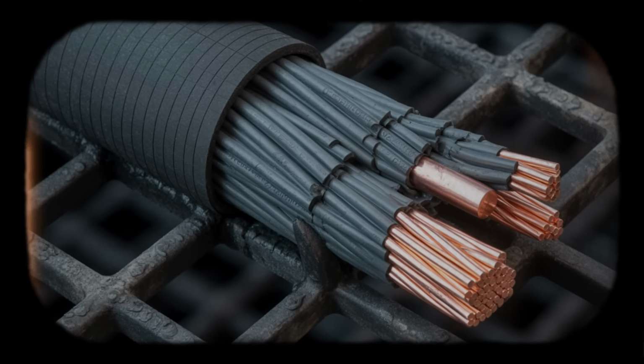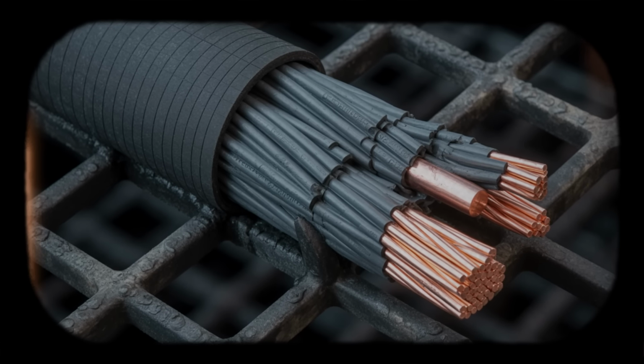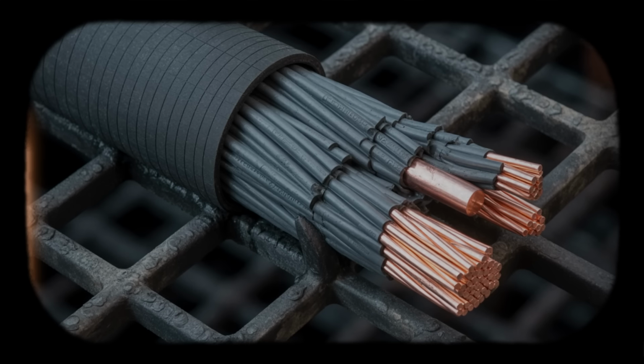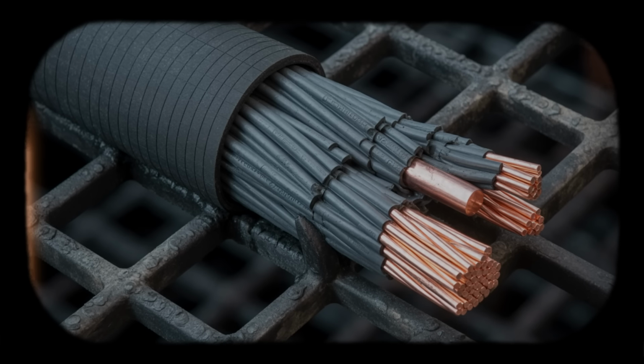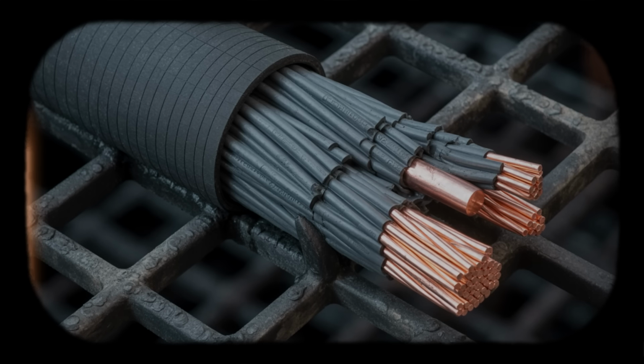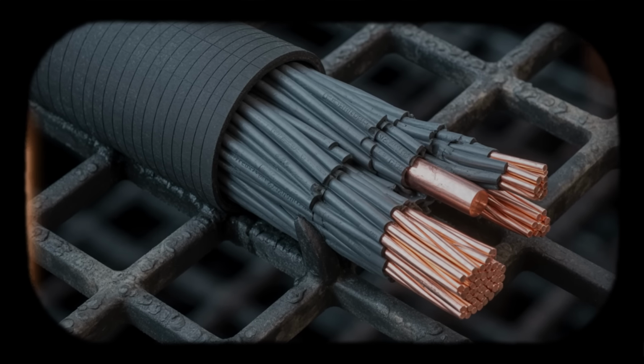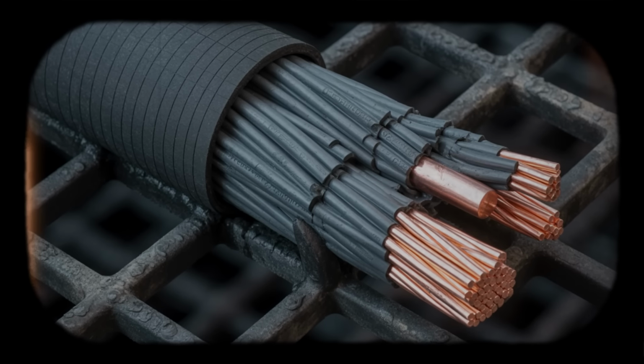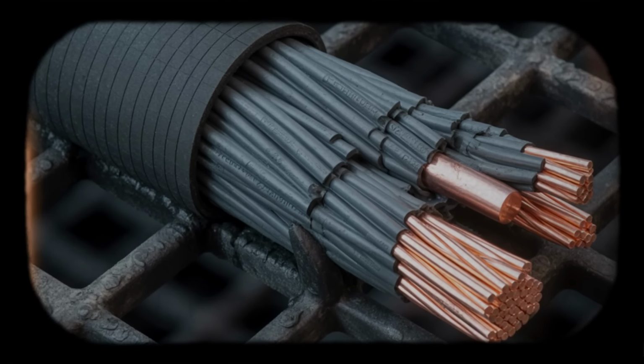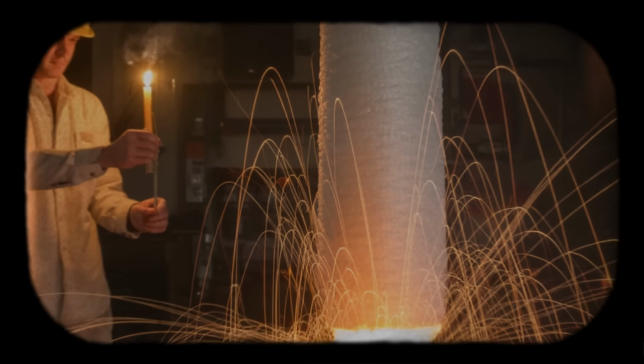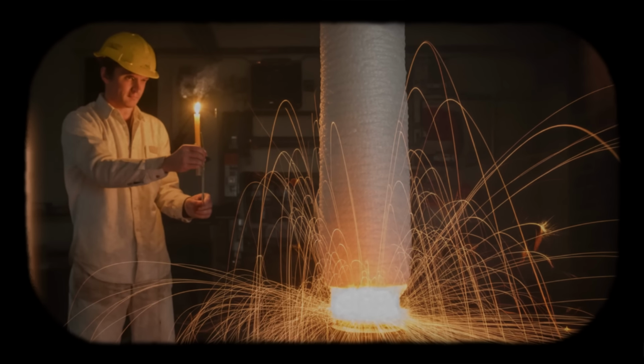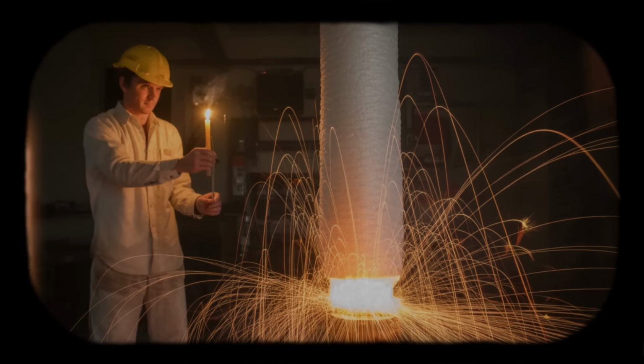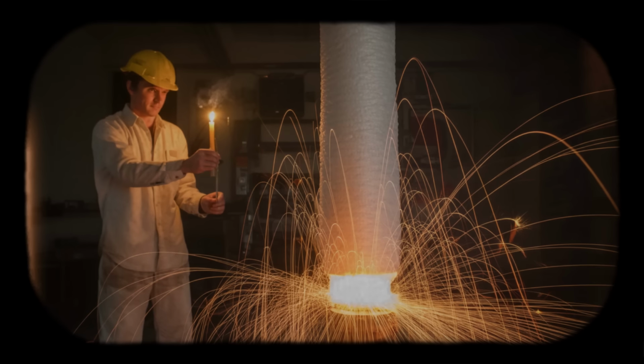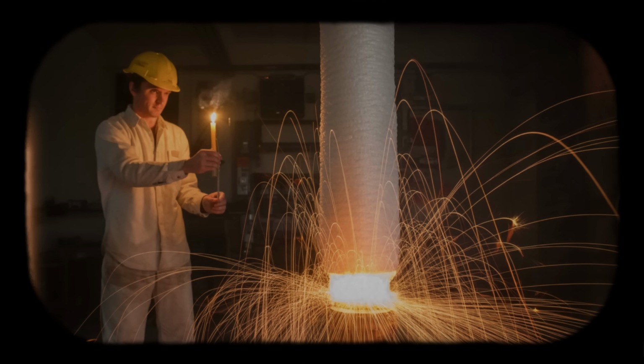When these materials burn in a confined space, they produce intense heat and thick smoke. Oxygen is drawn into the penetration from both sides, feeding combustion. The Preliminary Investigating Committee report documents the spread pattern. Propagation occurred vertically and horizontally along cable trays. Fire does not simply burn in place, it follows fuel. At Browns Ferry, the fuel consists of thousands of cables arranged in ladder rack trays that run horizontally across the ceiling and vertically along walls. Each cable is a potential wick.